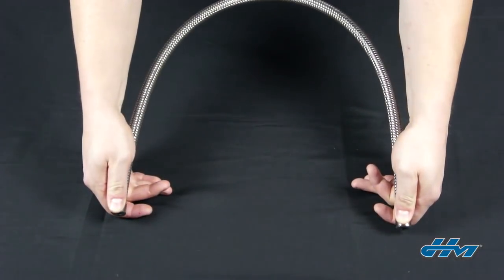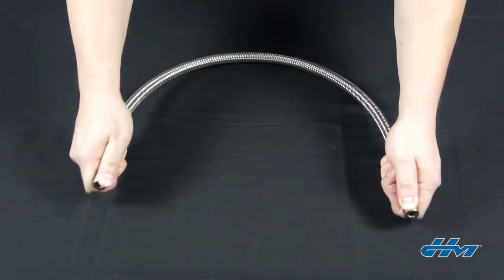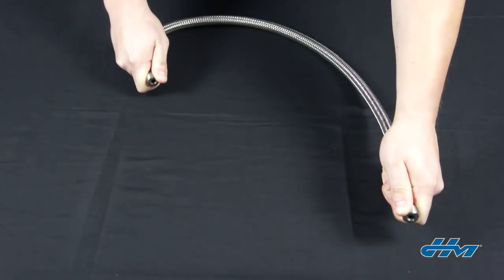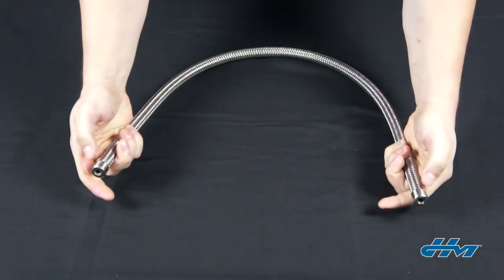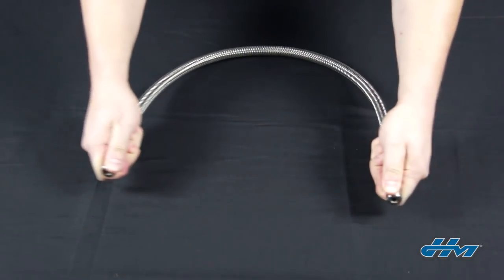Installing the hose in a loop is a great way to accommodate both vertical and horizontal movements. Don't stretch the hose with its live length between two end points. This puts a huge amount of stress behind the fittings, which is where the hose is most likely to fail. Do ensure that there is enough live length for the hose to function properly.